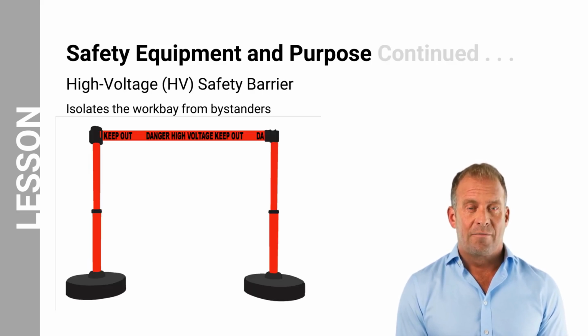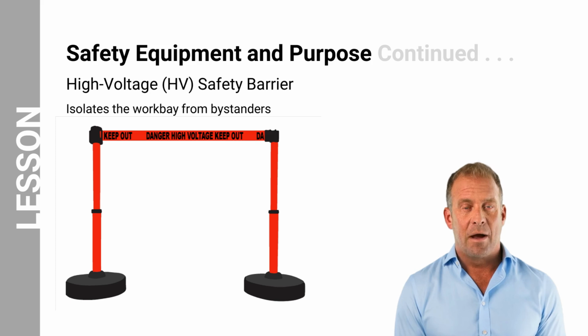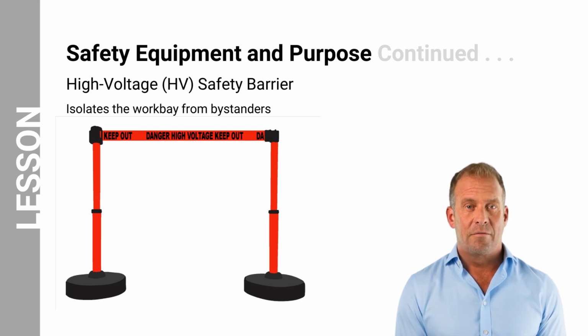Let us now look at high-voltage safety barriers. They are a type of barrier that isolates workbays from bystanders. They are typically made of a non-conductive material, such as plastic or fiberglass, and are designed to prevent people from accidentally coming into contact with high-voltage electrical equipment. When choosing high-voltage safety barriers, selecting ones rated for the voltage and current levels of the high-voltage electrical equipment you will be working with is essential. It is also important to choose barriers that are the correct size and shape for the workbay in which you will be using them.